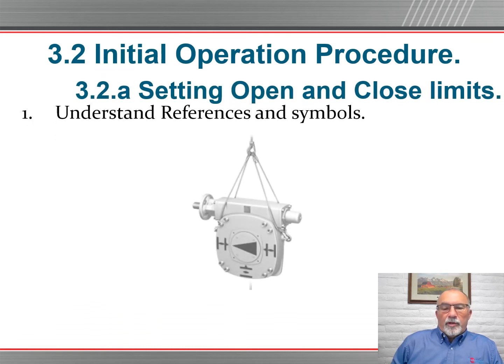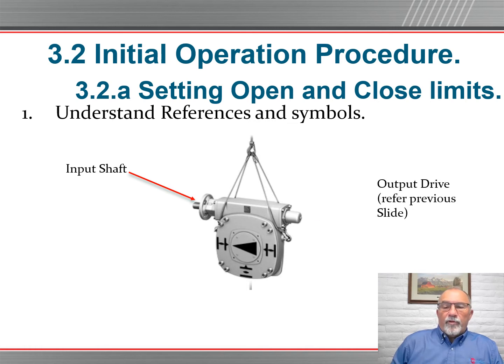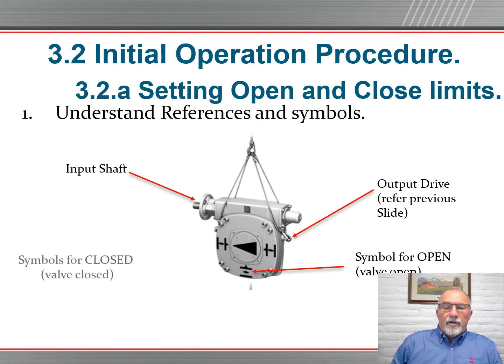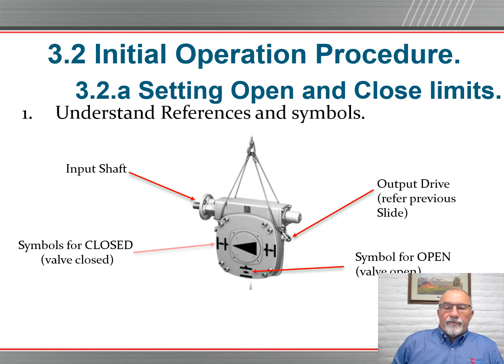Understand the references and symbols below. There's typically your geared operator. Sometimes these will ship separate from the valve, so don't be surprised if you're watching the contractor install this during the process. You have the input shaft, or where the hand wheel is located, or the electric operator is located. Output drive, refer to the previous slide if you have a question about the output drive. The symbol for open is a simple line that is open in flow, and the symbol for closed is with your line crossways in flow, simulating a closed pipe. Notice there's 2 places, whether it's clockwise or counterclockwise direction, you've got 2 closed locations available.